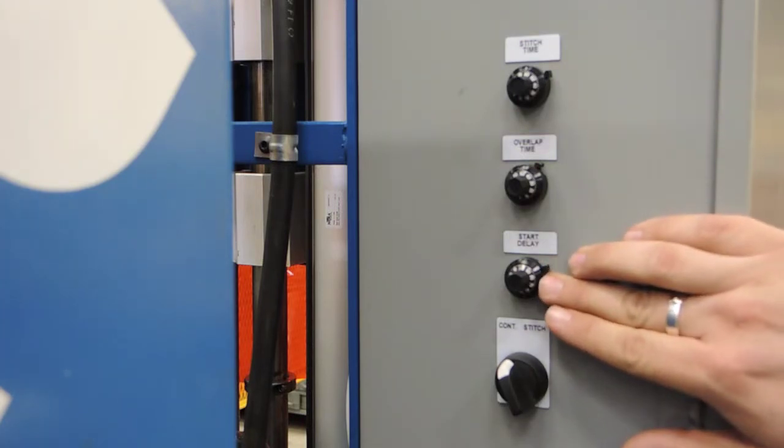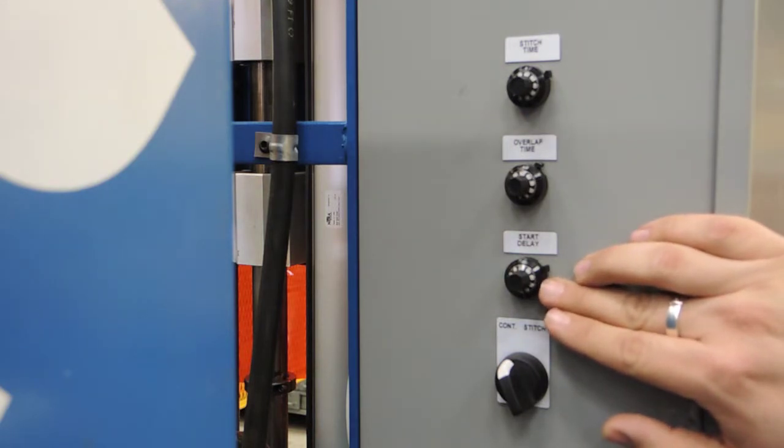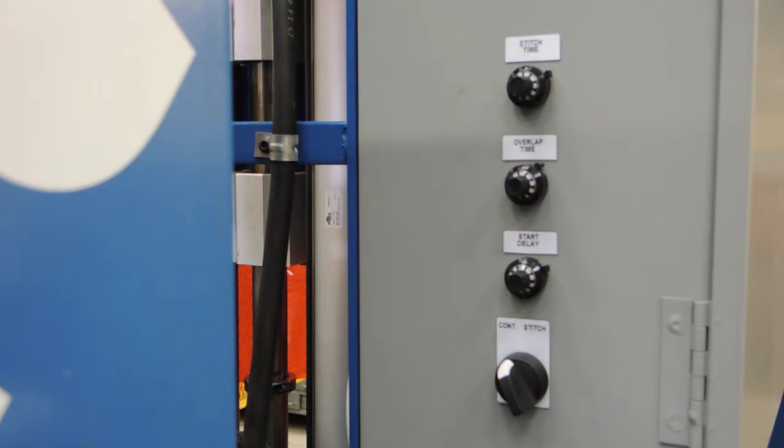Start delay is the amount of time the torch remains stationary while it is still on to develop a puddle before rotation is started. And the switch at the bottom switches from continuous mode to stitch mode. And again, stitch mode is set for four welds 90 degrees apart.